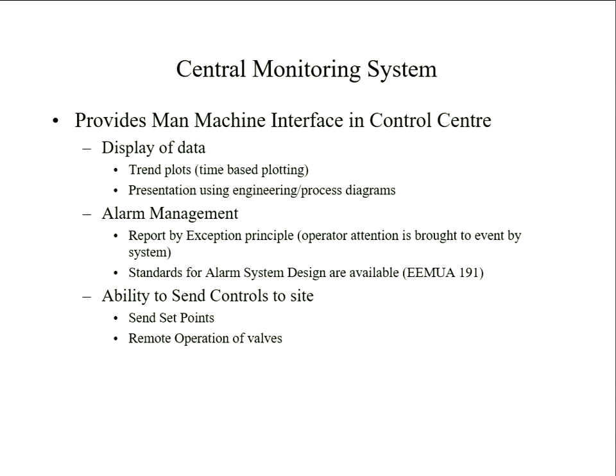They do have the ability to send controls to site, but what they're doing is sending the set point. So they'll say, I can type in 43 flow at compressor X, and it will send the 43 out. But the actual control of that compressor and ensuring that the compressor is flowing 43 is done by the site controls, not by the SCADA system. That's too slow. You don't put that in the loop.